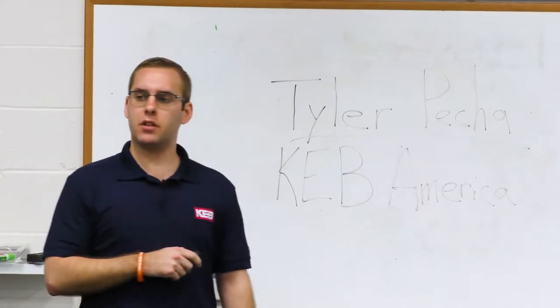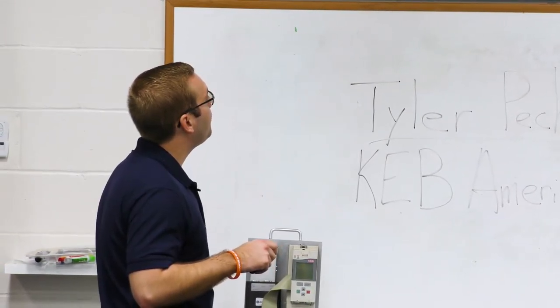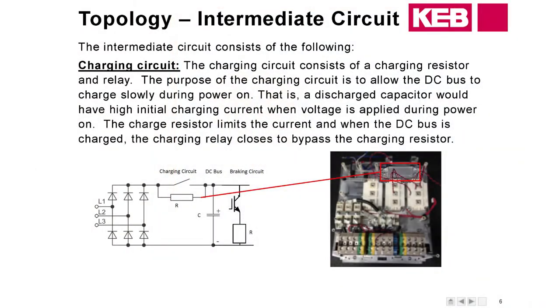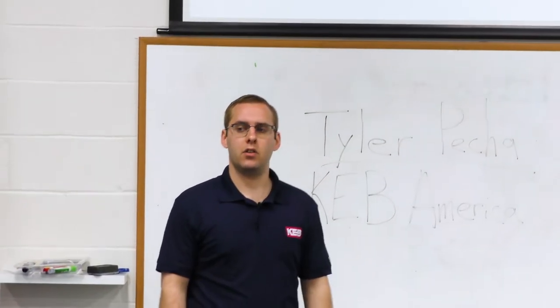Moving on to the intermediate circuit — we're going to have the charging circuit up here in the corner. This is used on initial power up. Due to how a discharged capacitor behaves, if you were to initially power up without this charging circuit there would be a large inrush of current that would actually cause damage to internal components of the drive. To limit that inrush, we run the current through a resistor, and then as soon as the DC bus charges up we bypass that resistor and connect directly to the line.